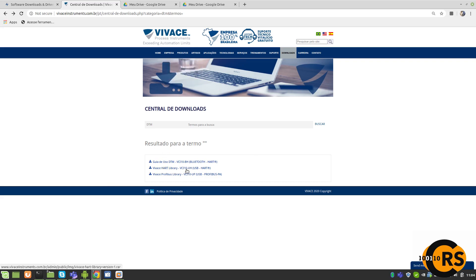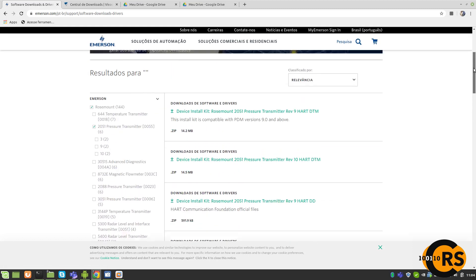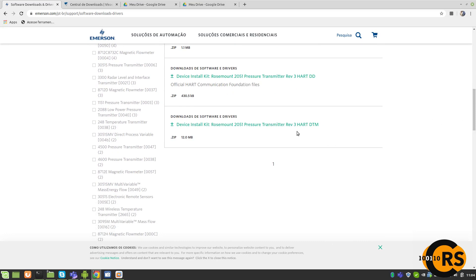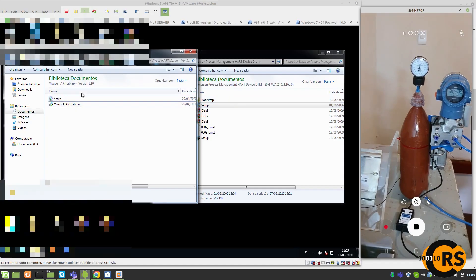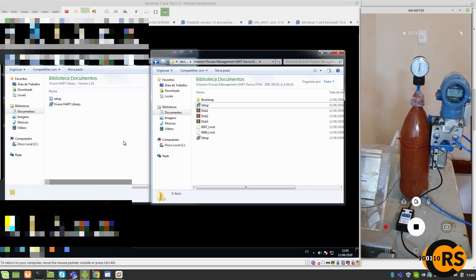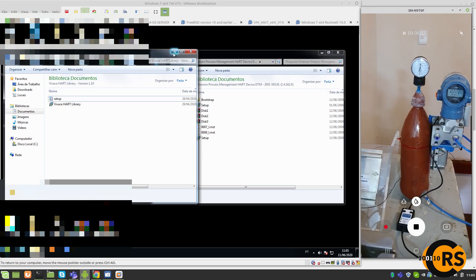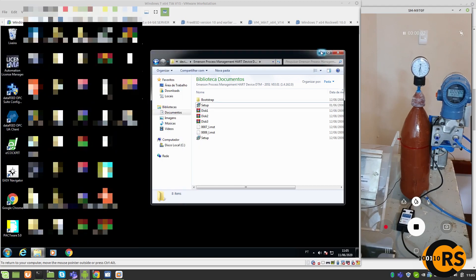Here we are on Vivace's website, where we can download the HART library for the VCI-10. When you download this file you have the DTM for their whole device. Here we must also download the DTM from Emerson for the Rosemount 2051 — here's the DTM for the transmitter. When you download these files you can install them on the machine where the FDT/DTM software is installed. So we have the DTM files from Vivace and from Emerson.